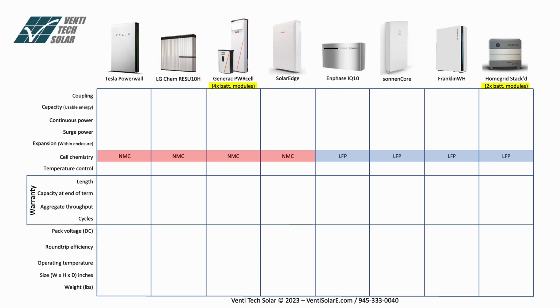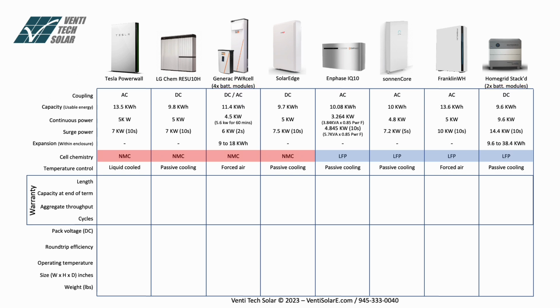Let's start with mentioning that the Generac and the Home Grid have been configured to match or align with the 9.6 to 13.6 kilowatt hour from the rest of the vendors, which are one solution, one capacity per enclosure. So as far as values, we have coupling, AC for the Tesla, DC for the Chem, DC or AC for the Generac, DC for SolarEdge, which I question since they have to use SolarEdge inverters. I would call this an AC couple system instead of DC, but technically it's DC. The Enphase is definitely AC because within the enclosure you have the microinverters, which could be the same microinverters that you use for the solar panels. SonnenCore is AC, FranklinWH AC.